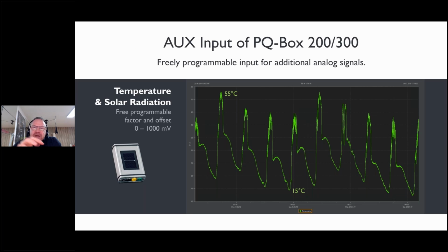With the fifth current input, which we call the aux input, we are absolutely flexible. You can measure the temperature of your transformer with the harmonics or the load. You can measure the sunlight radiation at a solar farm, the radiation in watts per square meter, relative to the load of the big solar farm. So any active sensor you can connect to our analyzers, and we can even trigger on temperature or differential current, so endless applications are possible here.